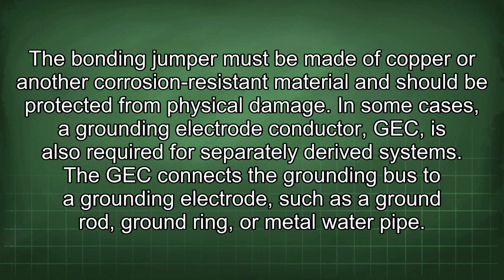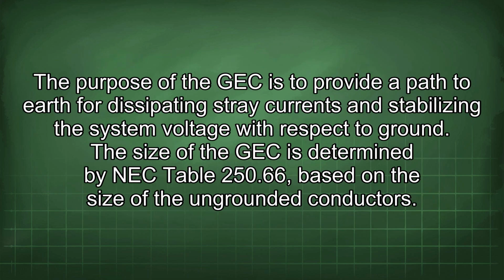In some cases, a grounding electrode conductor (GEC) is also required for separately derived systems. The GEC connects the grounding bus to a grounding electrode, such as a ground rod, ground ring, or a metal water pipe. The purpose of the GEC is to provide a path to earth for dissipating stray currents and stabilizing the system voltage with respect to ground. The size of the GEC is determined by NEC Table 250.66 based on the size of the ungrounded conductors.